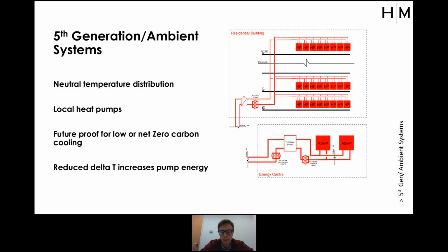So this system works quite well with heat pumps, because, and I didn't point this out in the previous slides, heat pumps, or certainly air source heat pumps, operate very efficiently around 30+ degrees, around that sort of envelope, and they don't have very good operation below that because of the step or lift temperature you have to consider. But they work very well with an ambient system, be it neutral temperature, or there are very many terms for this type of system, but they operate very efficiently, and the COP increases can be significant.